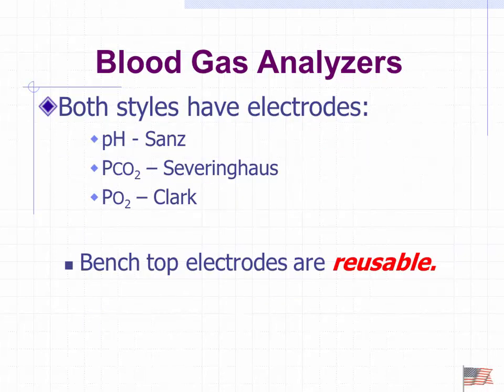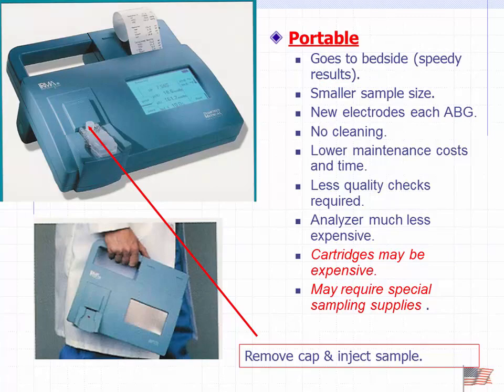Both types of analyzers have these three electrodes. If you remember back from 1085, probably not. Probably put it out of your mind as quickly as you could, but here it is back again. The Sanz electrode, which is measuring pH, the Severinghaus, which is measuring PCO2, and the Clark electrode. And again, in the benchtop model, they're reusable.